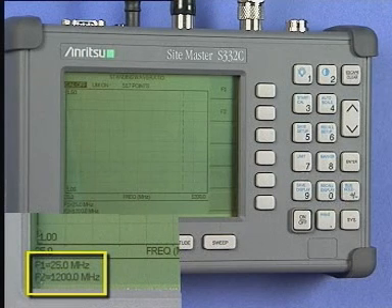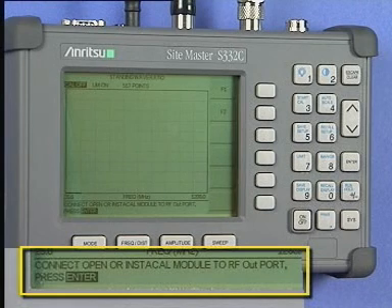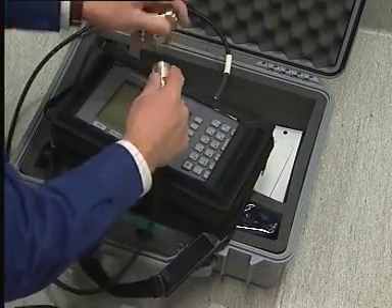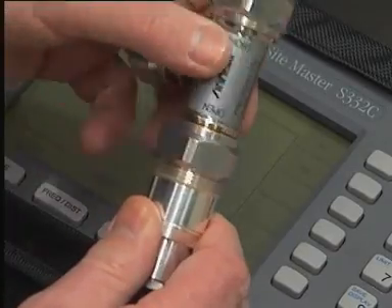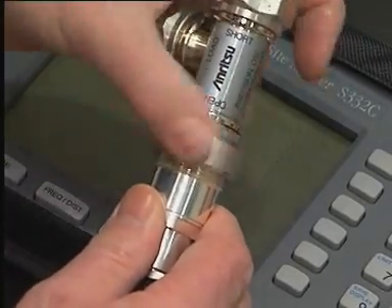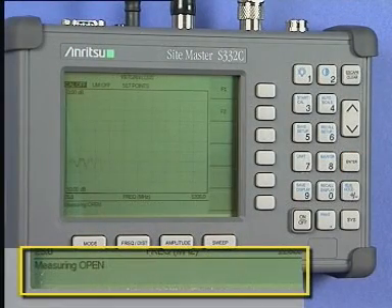Assuming the frequency range has been set, we can now go ahead with the calibration. If you have set the F1 and F2 frequencies, then you are already in the Frequency Distance menu. Press the Start Cal key. At the bottom of the screen you will see the text 'Connect Open or Instacal Module to RF Out Port', which is asking you to connect the calibrated open circuit to the extension cable connected to the instrument. When you have done this, press the Enter key and the instrument will sweep and measure your chosen band of frequencies.